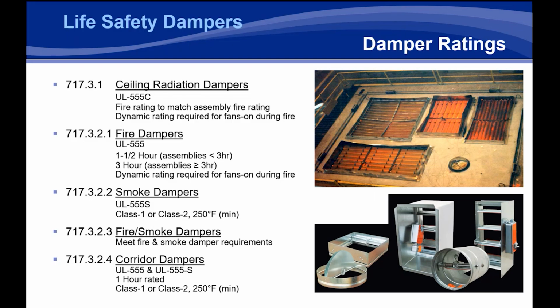So in order to do that, there's no clear-cut way in the code to shut the fans down. There's nothing in the mechanical code now for air handlers that supply more than 2,000 CFM other than requiring smoke detectors on common returns. So that is one option. There are other options to create a static system as well to shut down the fire. There's nothing specifically in the code for these air handlers that forces them to shut down a certain way. So right now, it's up to the jurisdiction to either allow a thermostat or something that'll see heat, like a fire damper, that'll shut the system down, or a fire smoke damper, or you can put a smoke detector in place to be able to shut that down under detection of smoke. That's not something that building code will probably change anytime soon.